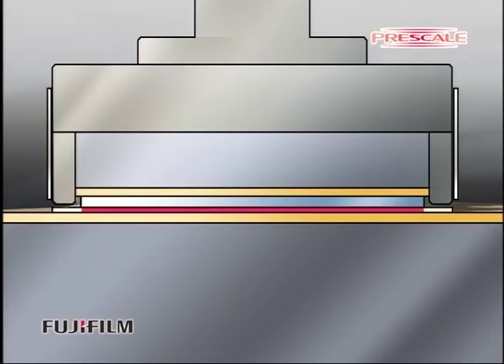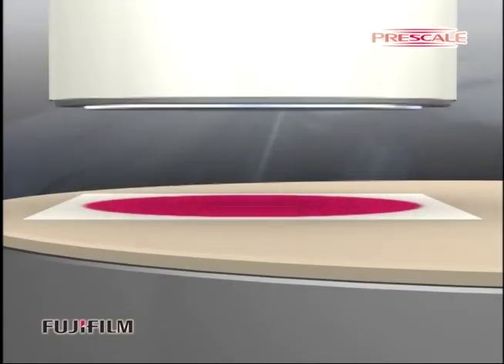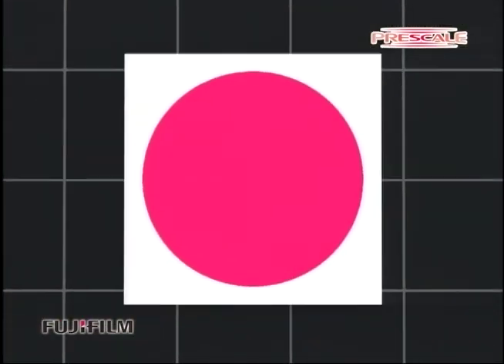Then, separate the polishing head from the rotating level block and check the color development on the Prescale. If the wafer surface is flat and smooth and the device has good balance, the color will develop evenly as shown.